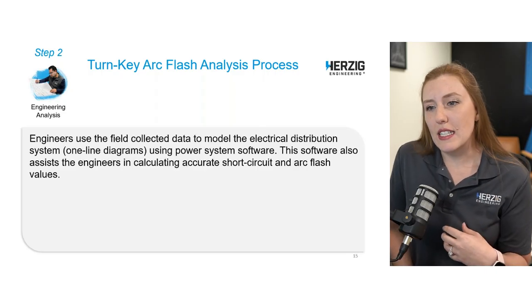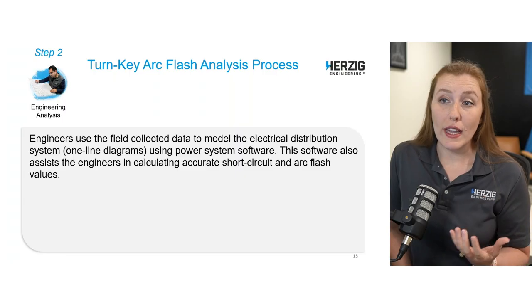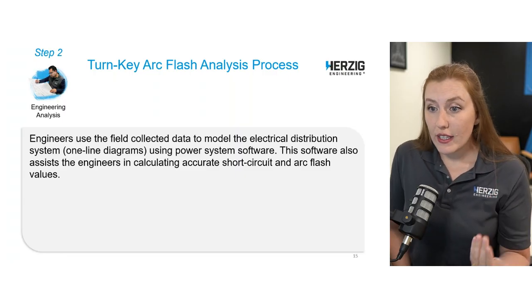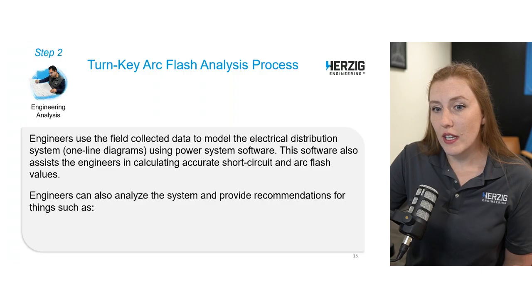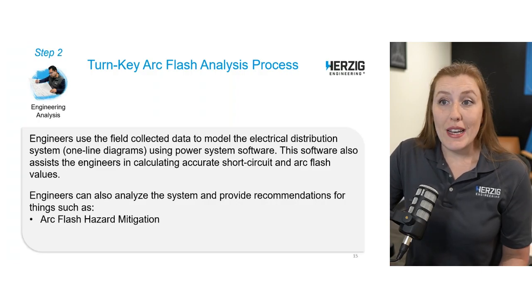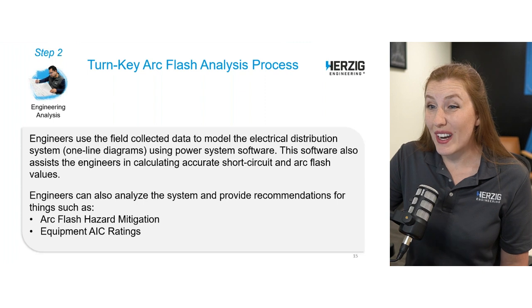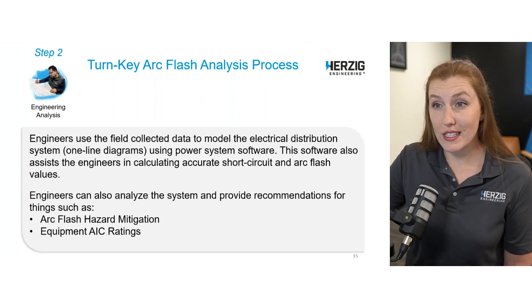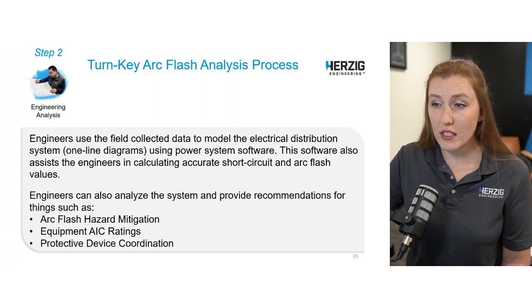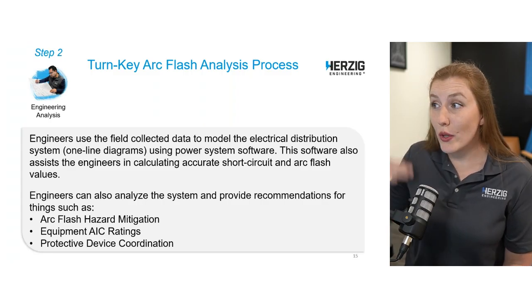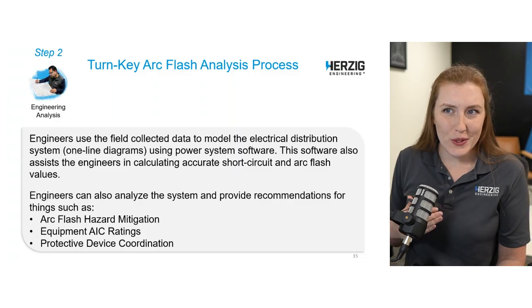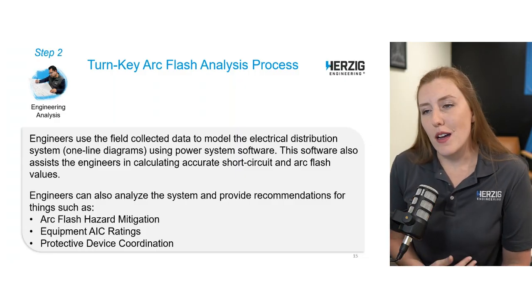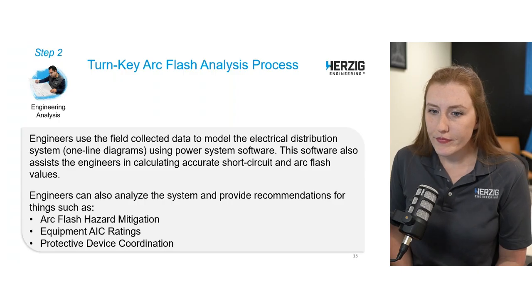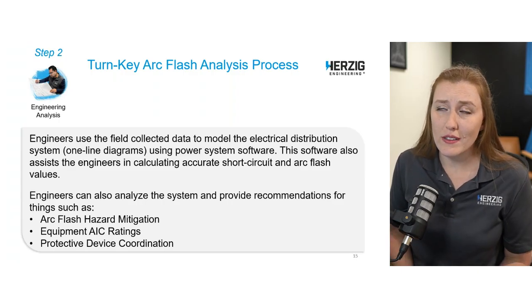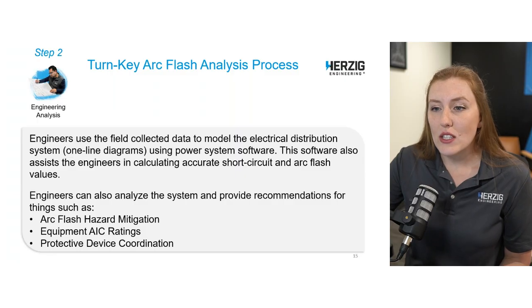Then it gets brought back to the office, and the engineers will use that field collected data to model the distribution system on a one-line diagram. And then they'll run the calculations for short circuit and arc flash calculations. We'll look at mitigating the hazards, looking at your equipment ratings themselves. If there was a fault, would it even stand up to that available fault current? And protective device coordination. Will things actually operate in the order that they're supposed to? That is also a requirement to be done every 5 years at a minimum. So we're getting multiple studies done at once, but it's all in one report.